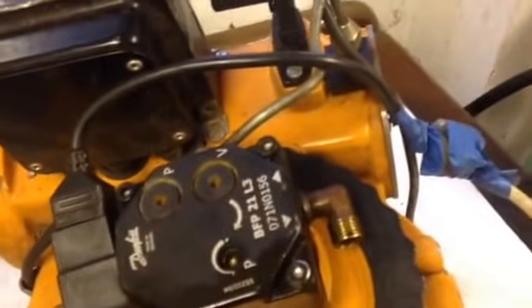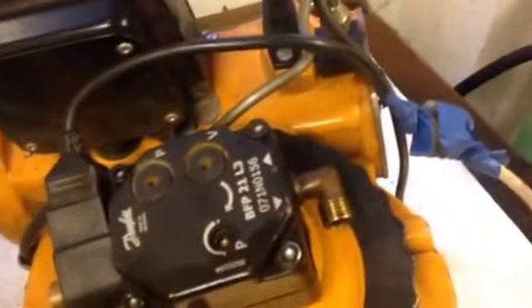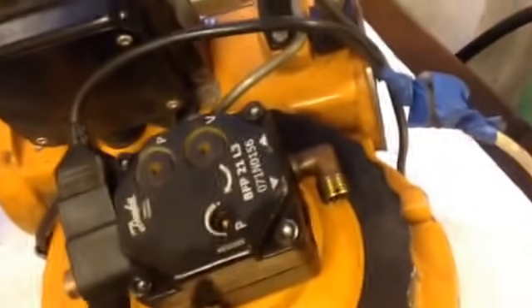If it hasn't been able to see there's a flame, for example if this magic eye is broken, it won't continue, because what it thinks it's doing is blowing loads of vapour into the boiler that isn't ignited, which could cause an explosion. So it's quite clever.